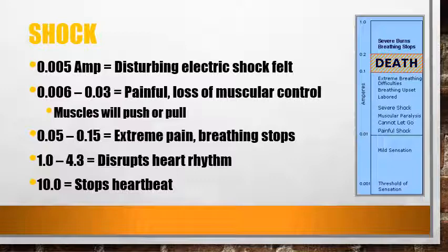At 5 to 15 hundredths of an amp, extreme pain will be felt, and even the possibility of your breathing stopping. At 1 amp to 4.3 amps, your heart rhythm will be disrupted by the electrical shock. And anything greater than that has the potential of stopping your heartbeat.